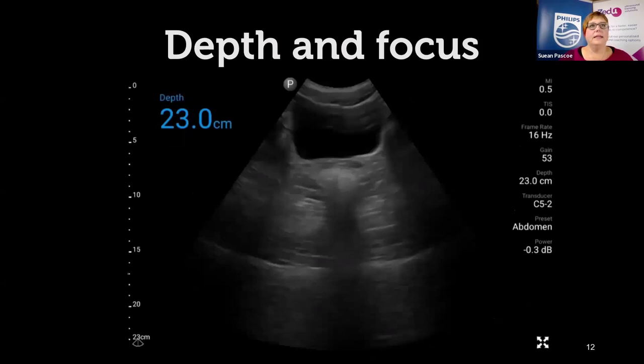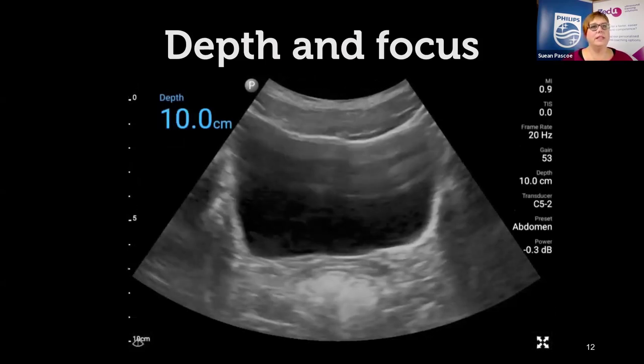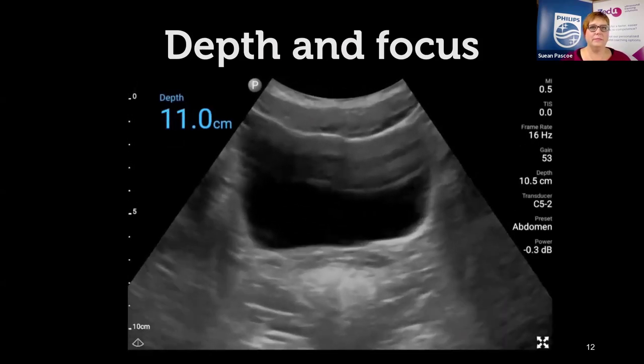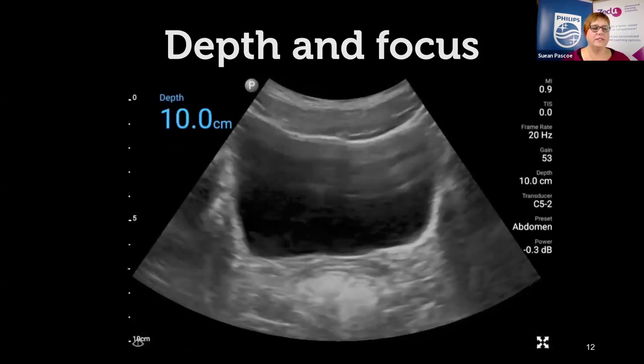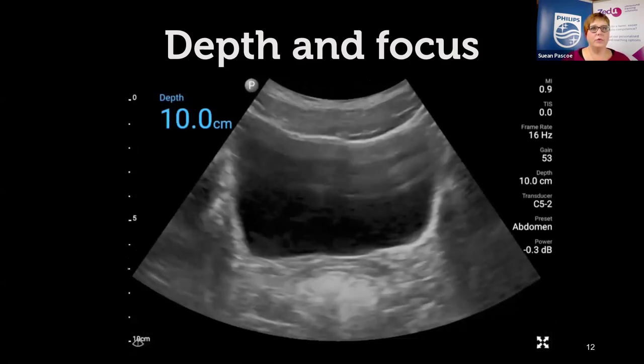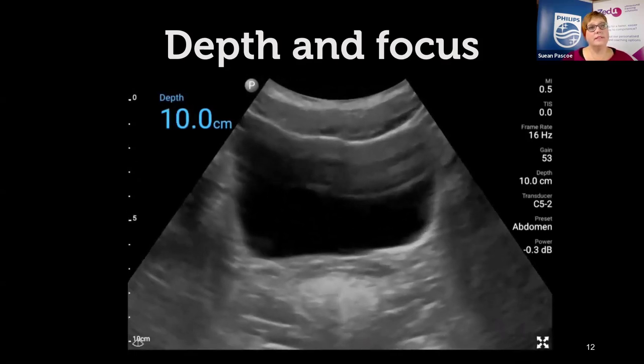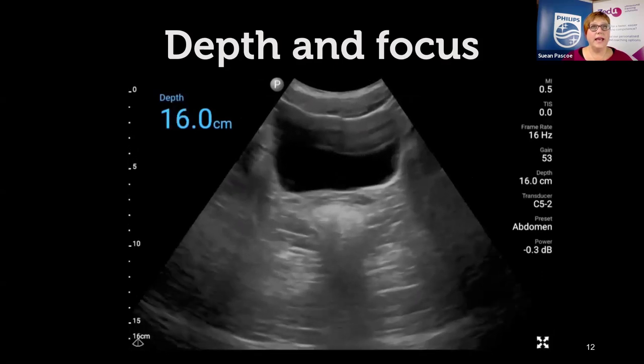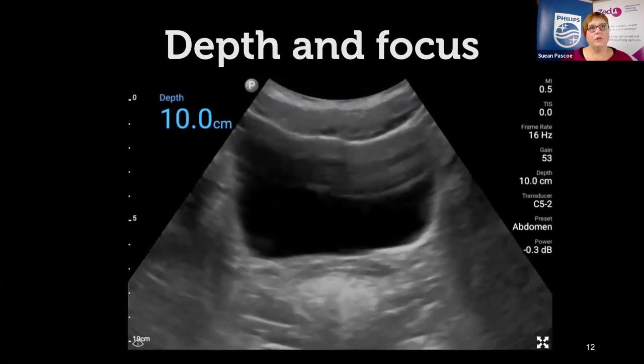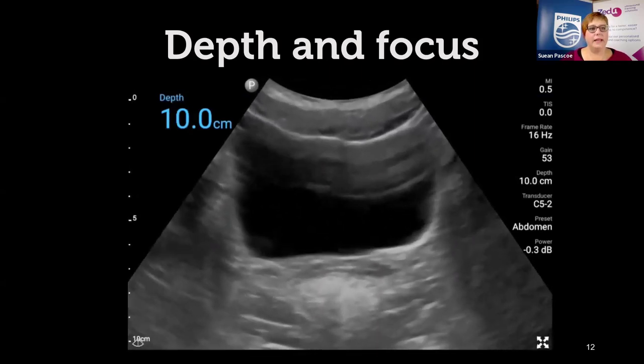Make sure depth and focus are set correctly — you want the bladder to fill the screen. As you adjust the depth in real time, set it so you can see a couple of extra centimeters behind your region of interest. On handheld and point-of-care systems, getting your depth setting correct is crucial for ensuring the focus is at the right place. If you have a focal zone on your cart system, you need to set it at the back of the bladder.